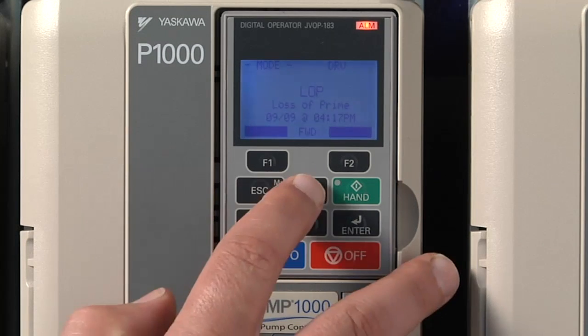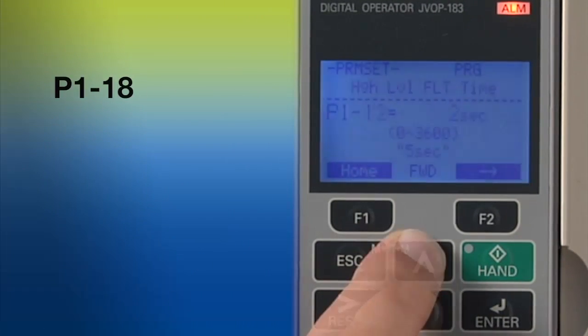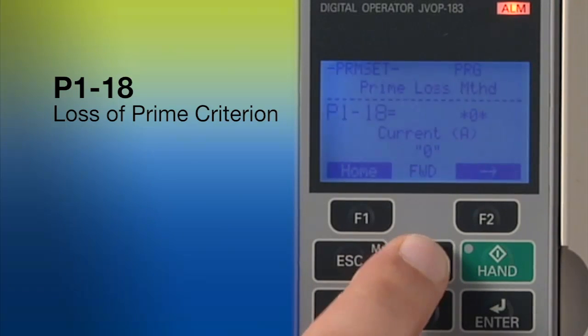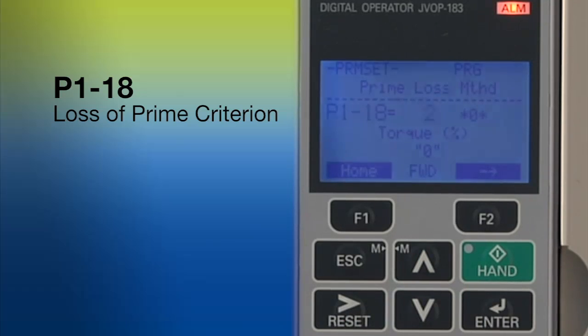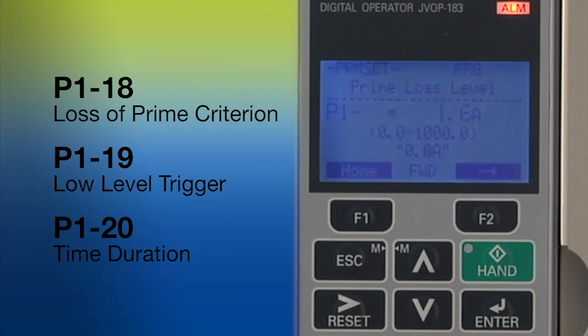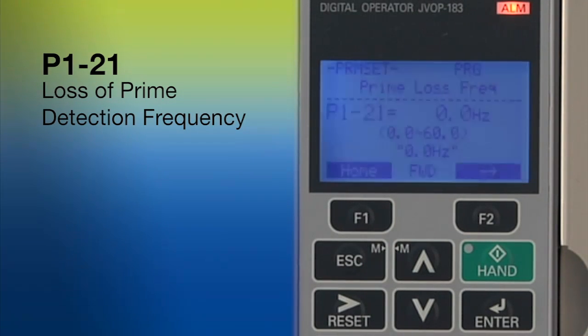You can adjust the definition of loss of prime by using a set of P1 parameters in the programming menu. Parameter P1-18 sets the criteria that IQ Pump will use for determining loss of prime — choose motor current, power, or torque. Both P119 and P120 fine tune the definition. P119 allows you to set the level of low current, power, or torque that triggers a loss of prime event. P120 lets you set how many seconds the loss of prime must last before it triggers a fault. Setting P121 sets the speed your motor must exceed before IQ Pump recognizes the change as loss of prime.